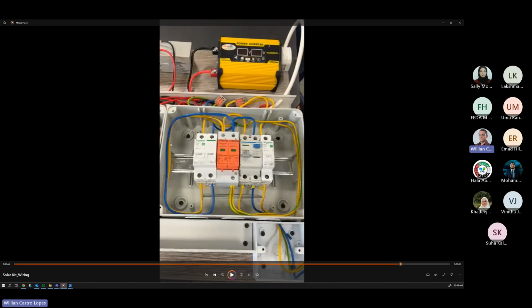This circuit breaker is connected to our surge protective device. A surge protective device protects the installation against over voltage, for example in a real application against lightning or a high voltage. Imagine a high voltage wire touches the low voltage wire and the voltage increases very fast in the system. The surge protective device will make a kind of short circuit and drain the current to the earth. That's why we connect it to the ground, to drain the current and make sure the voltage in the system is not higher than the safety voltage for the circuit.